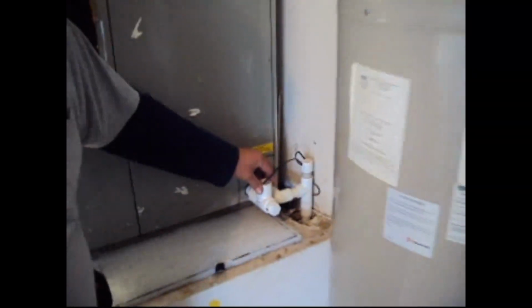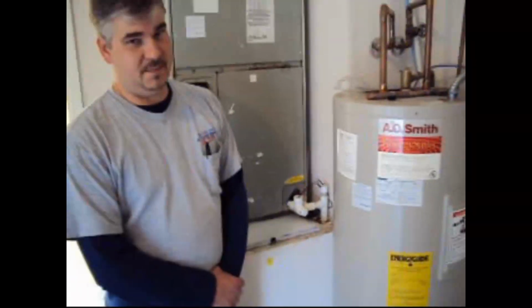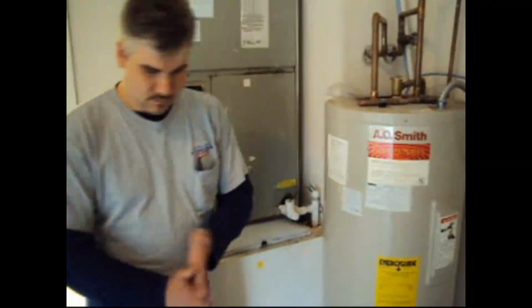of water. If it's full of water, your machine is not going to function, and you know that your drain is backed up. Now we've just checked this float switch and it's not backed up with water. The next thing to check is to see if your outdoor unit or your indoor unit are running.